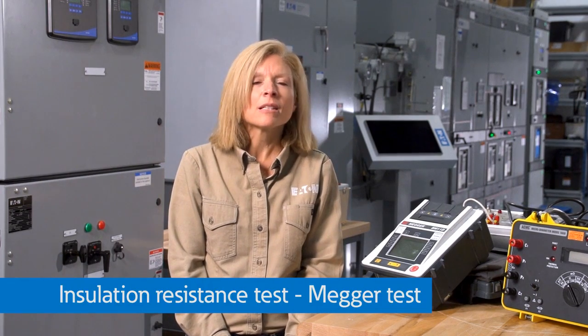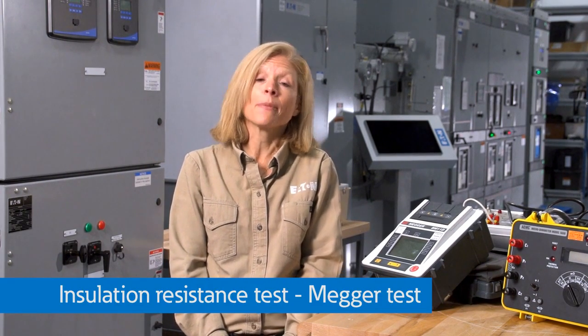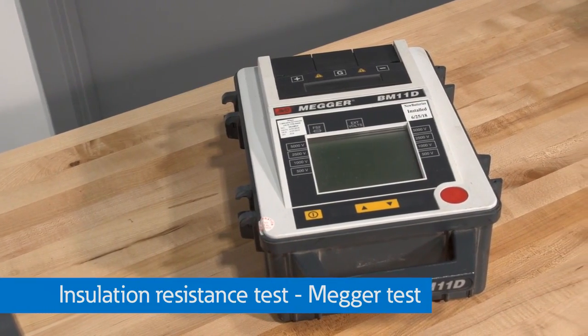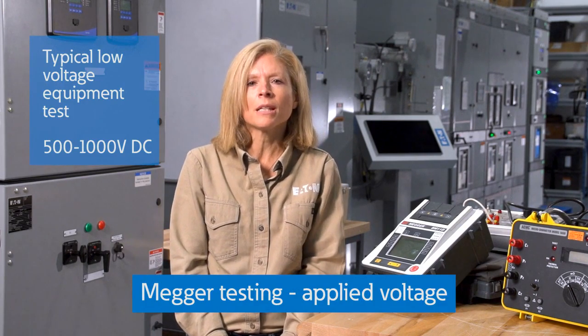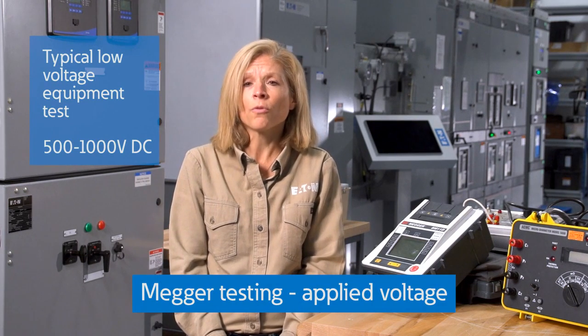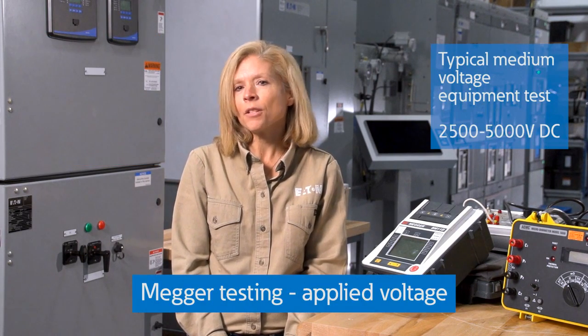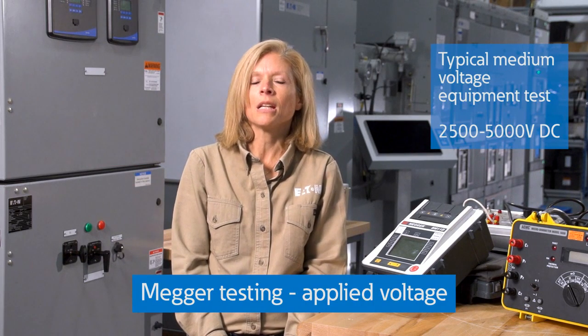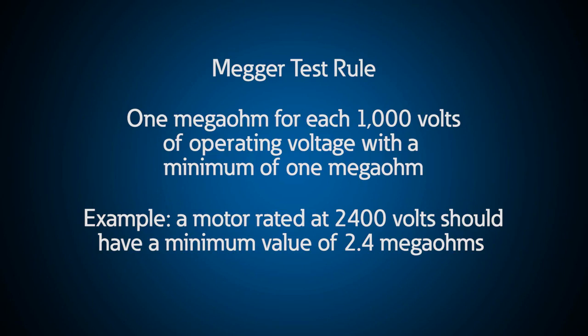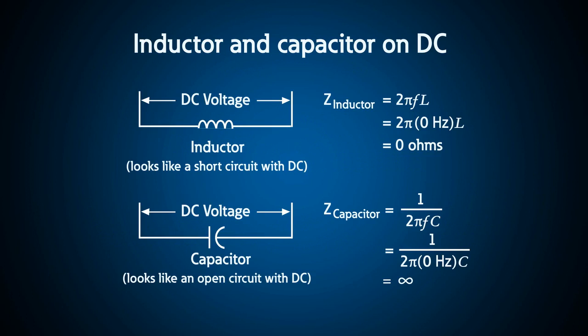One test would be called an insulation resistance test. That is also called a Megger test because of the brand name of the common equipment used for this test. A Megger test uses an applied DC voltage that generally would be 500 volts DC or 1000 volts DC for low voltage equipment, and about 2500 volts DC or 5000 volts DC for medium voltage equipment. The values will be typically measured in ohms or megohms, but can go up to gigaohms or teraohms. Because testing is done with DC, inductance and capacitance are not evaluated, and only the DC resistance is measured.